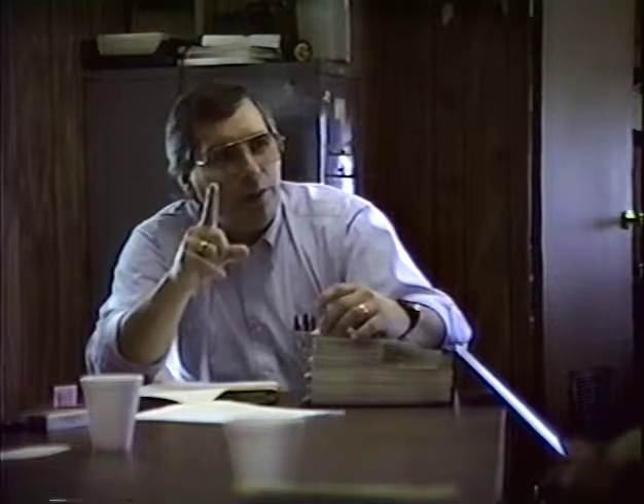The alarm comes on the standard annunciator panel, you hit the reset, or the silence button, acknowledge, whatever you want to call it, and the light stays on steady instead of flashing, right? We have this one different. It does three things: it flashes when it comes on, it goes steady when you acknowledge, and it goes out when you clear it.